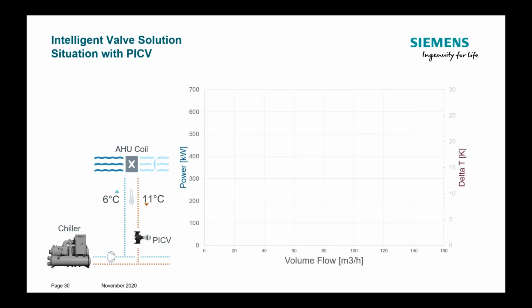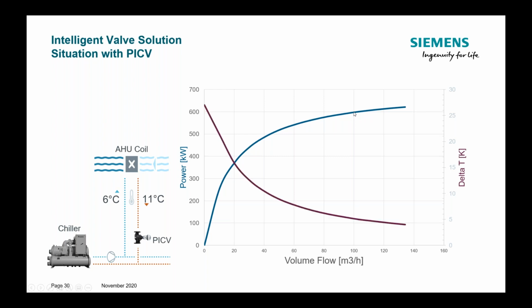We can see this also if we look at the transition curve of the coil. This might be the transition curve of the coil in this air handling unit from 0 to 100%. So here we go with a coil for roundabout 600 kilowatt at 100 cubic meters. Now, this is the DeltaT across this coil with the flow. So at low flows, at part loads, it's quite high. It's here on the right-hand side, 10 degrees at 40 cubic meters, which is a good value, 10 degrees DeltaT.